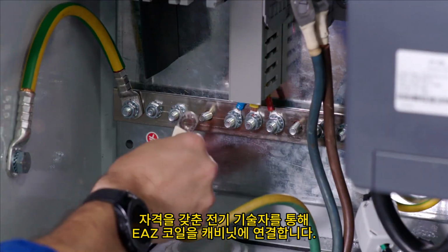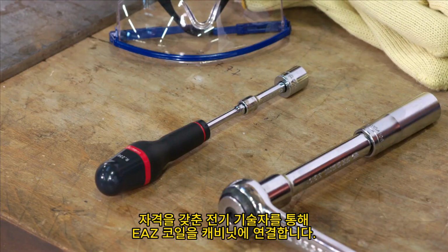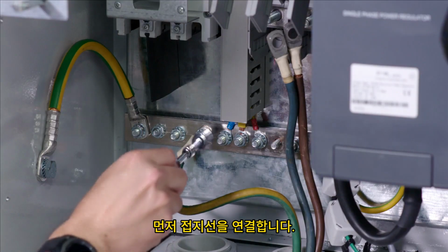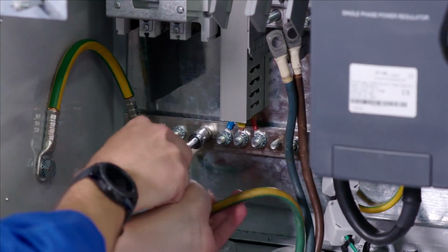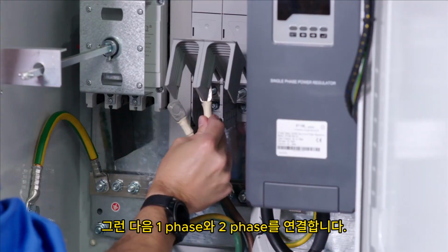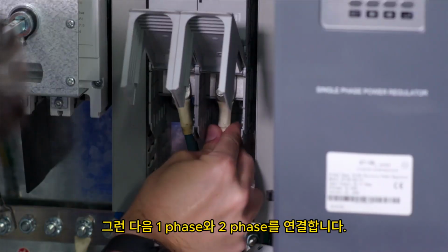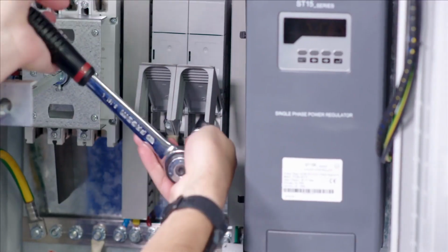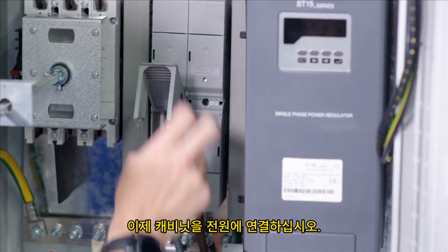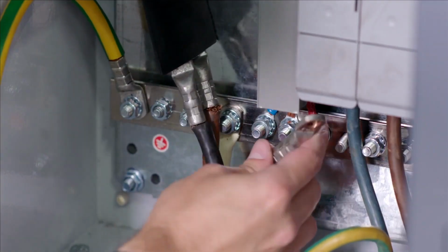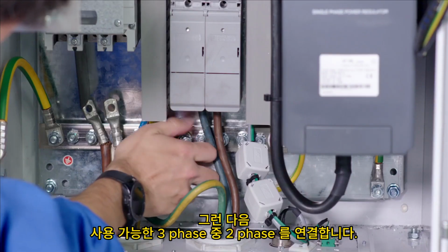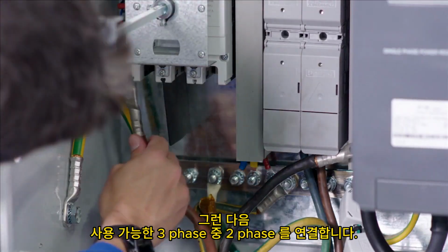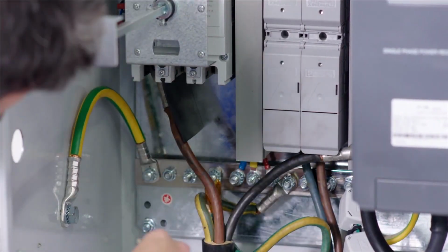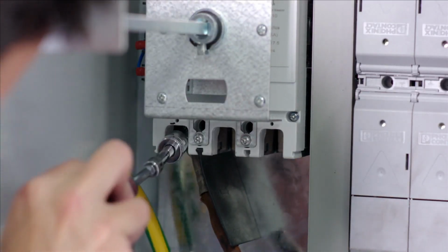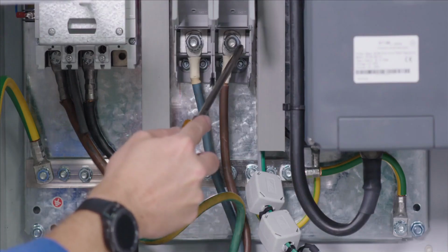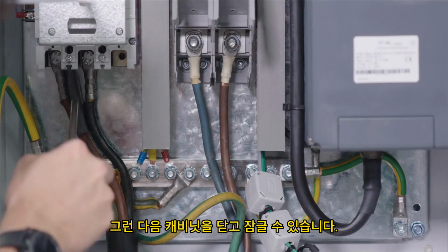Using a qualified electrician, connect the EAZ coil to the cabinet. First, connect the earth wire. Then connect phase 1 and phase 2. Now connect the cabinet to the mains. Connect the ground, then connect 2 phases out of the 3 available. Check all connections. Then the cabinet can be closed and locked.